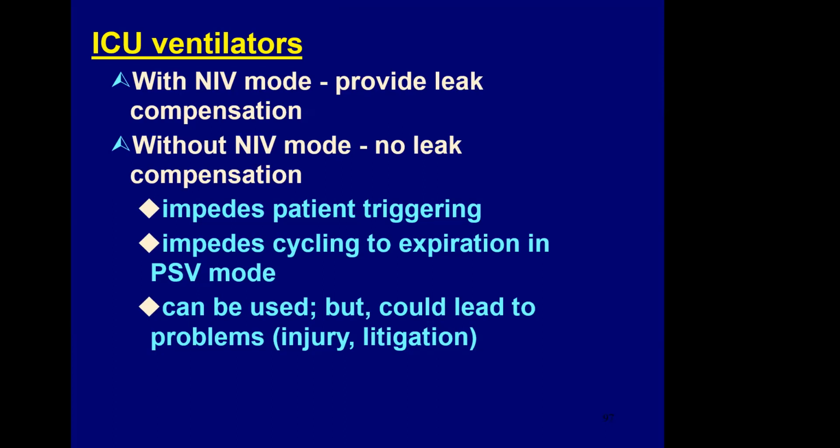It will also impede cycling to expiration when the pressure support mode is being used. It can be used without the leak compensation. These ventilators can be used, but it's not a good idea. It could lead to problems such as injury to the patient and, of course, litigation.